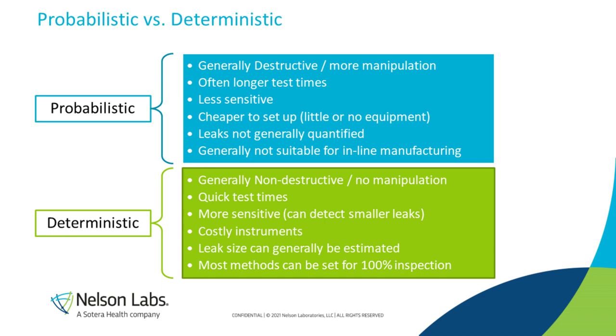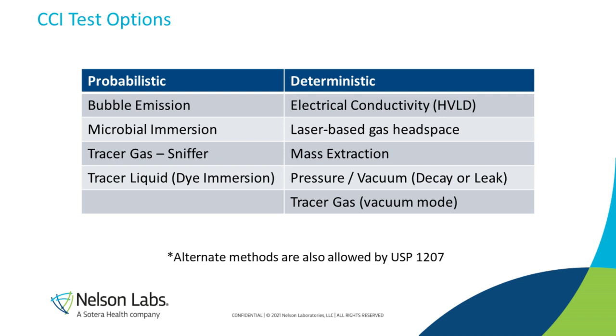Probabilistic and deterministic methods are really complete opposites. Where probabilistic methods are destructive, deterministic methods are non-destructive. Where probabilistic methods are slow and less sensitive, deterministic methods are fast and more sensitive. Where probabilistic methods are cheaper to set up, deterministic methods require costly instruments. And where probabilistic methods can't tell you what a leak size is, deterministic methods can often estimate a leak size based on numerical results. Nelson Labs offers bubble emission, mass extraction, dye immersion, and bacterial immersion testing.